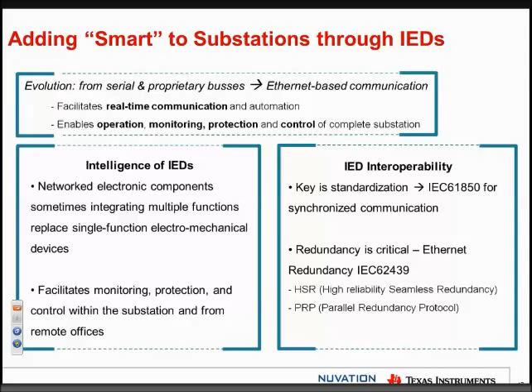As we look at the substation, retrofitting into a traditional system is key, which is where standardization and support for standards such as IEC 61850 is especially important. For a reliable system, redundancy for Ethernet-based communication is also key, with protocols such as HSR and PRP.